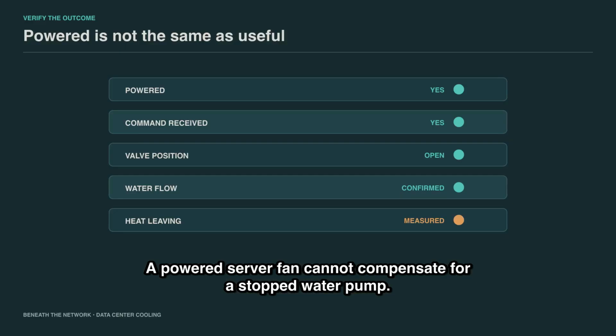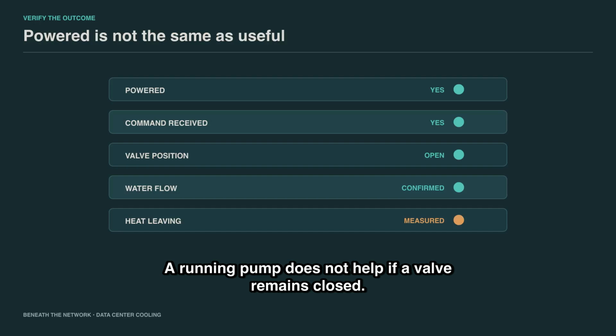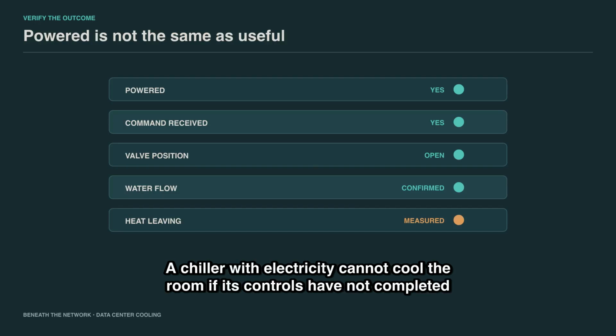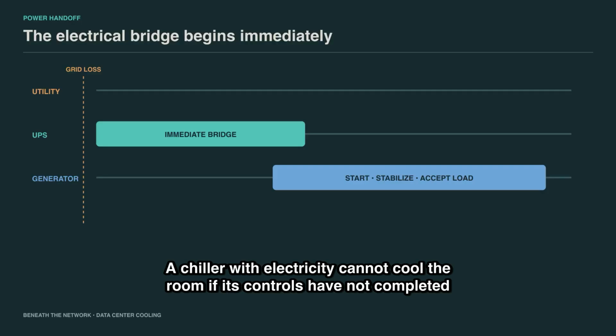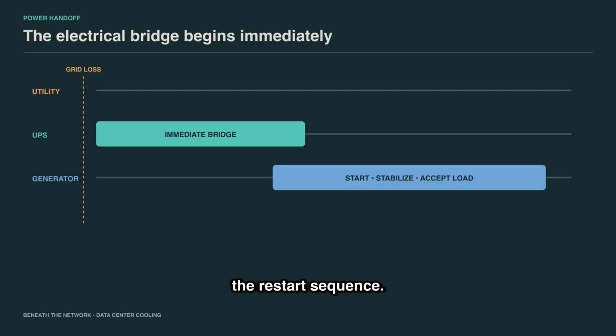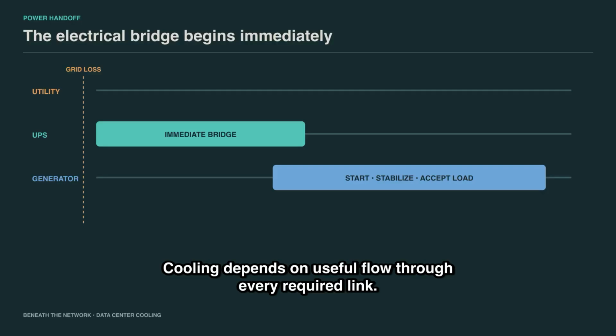A powered server fan cannot compensate for a stopped water pump. A running pump does not help if a valve remains closed. A chiller with electricity cannot cool the room if its controls have not completed the restart sequence. Cooling depends on useful flow through every required link.